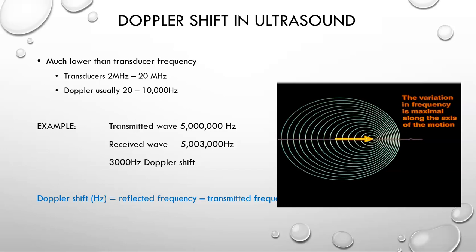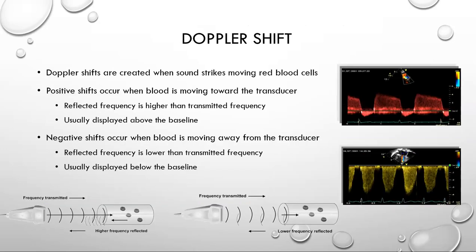For example, a transmitted wave might be a 5 MHz signal. The received wave will be only a small percentage changed — say, 5,003,000 Hz — and so the Doppler shift would then be 3,000 Hz. The Doppler shift equals the reflected frequency minus the transmitted frequency. Doppler shifts are created when sound strikes moving blood cells. Positive shifts occur when the blood is moving toward the transducer, and negative shifts occur when the blood is moving away from the transducer.